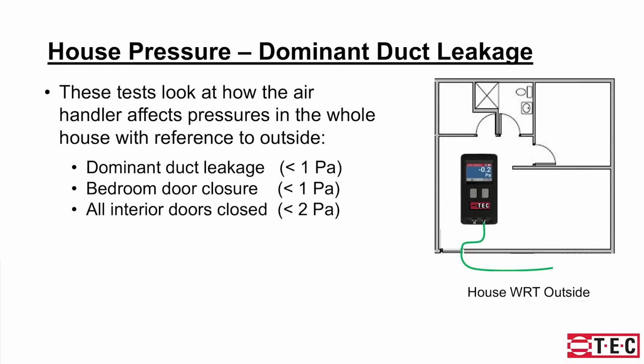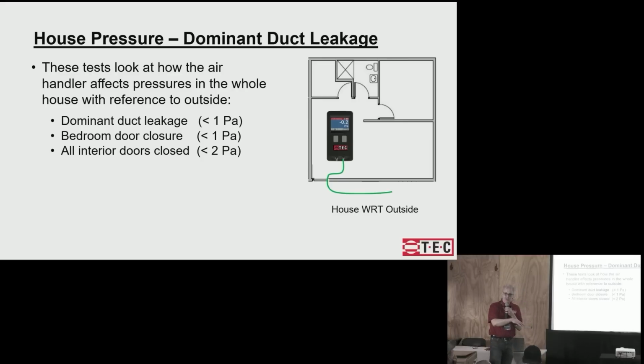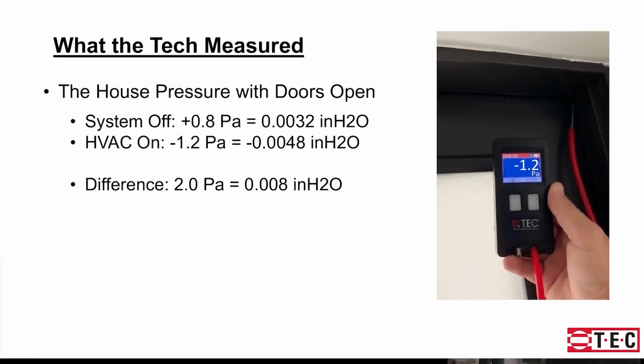The test is done by having the manometer inside the main living space, and you run the tube on the negative side outside. So you're measuring the house pressure on your positive with respect to outside. You take that measurement with the system turned off, and you'll get a number. Then you turn the HVAC system on, let it get up to full speed, and measure it again. And did it change? If your ductwork is all sealed and all the air that leaves is coming back to inside, the pressure shouldn't change.